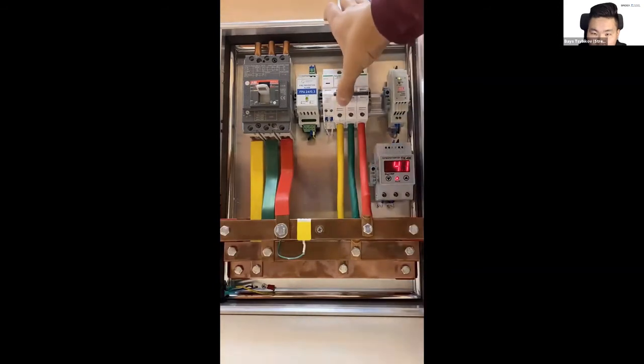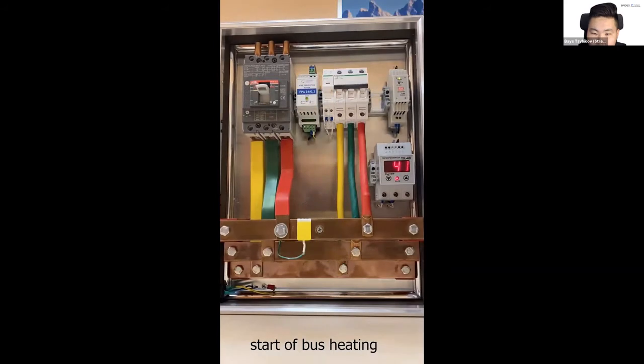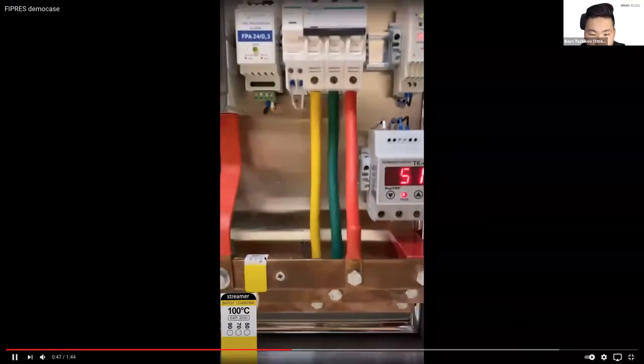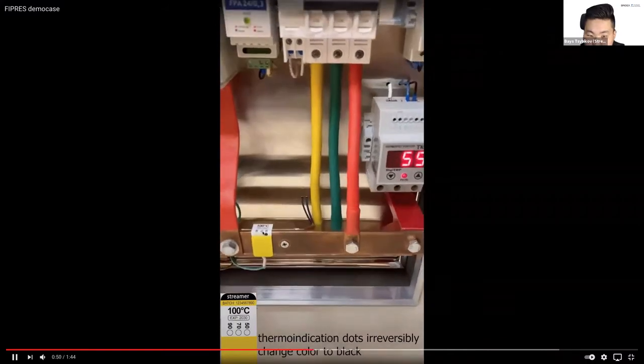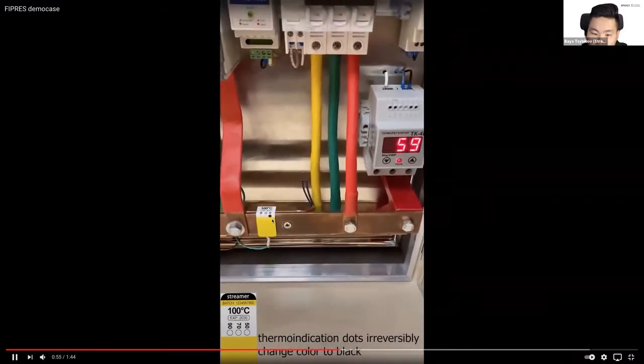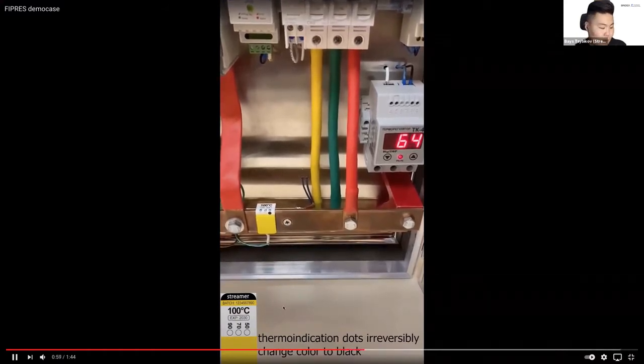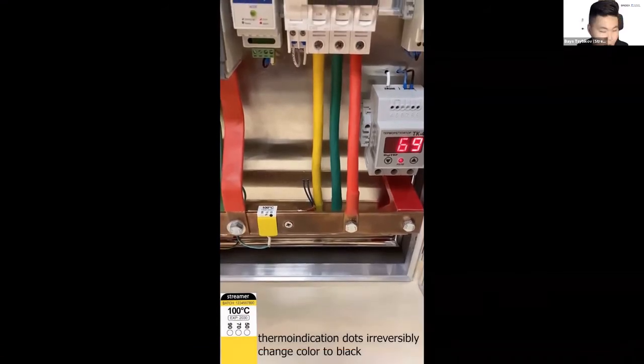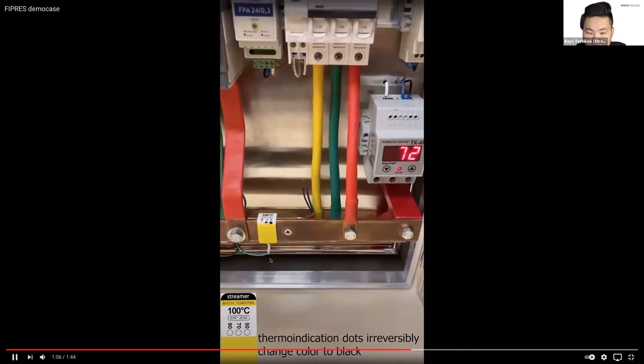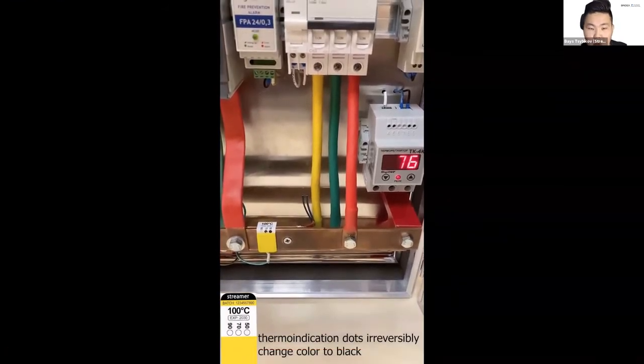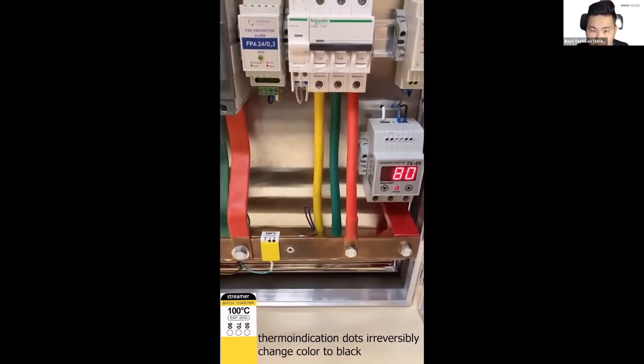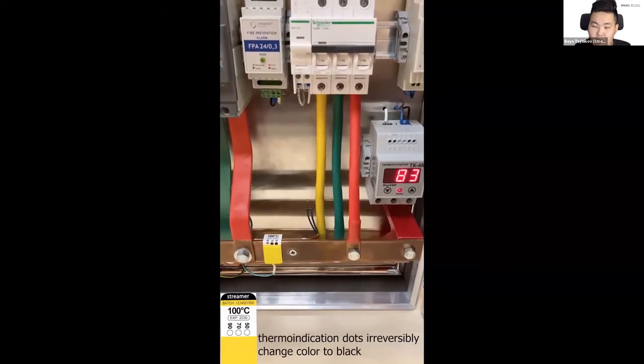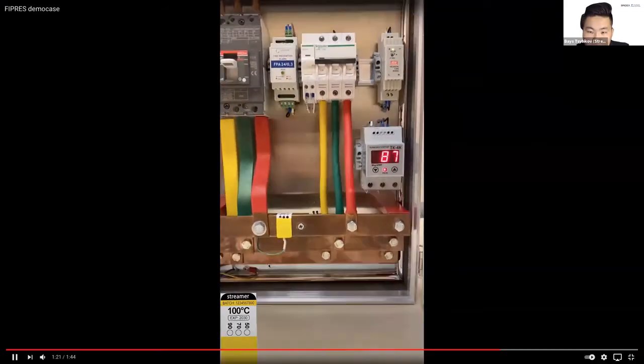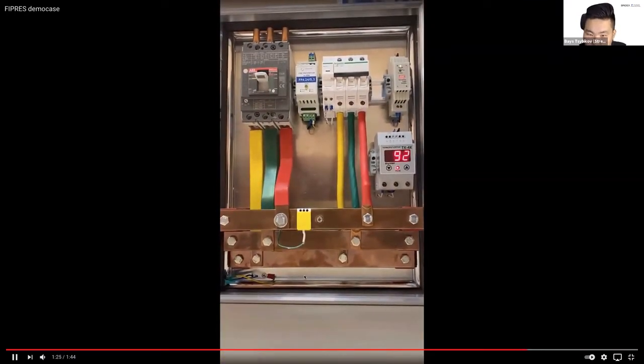And now we switch on the circuit breaker. At that moment, the heating starts. You can see the temperature is rising. Now we should control these thermal indication dots. You see at 50 degrees, the first thermal indication dot gets black. Now we're waiting for 70 degrees. At 70 degrees, the second dot also gets black. Now we're waiting for 90 degrees for the last dot and for 100 degrees for gas releasing. As you can see, at 90 we have all 3 dots black, and now we're waiting for 100 degrees.